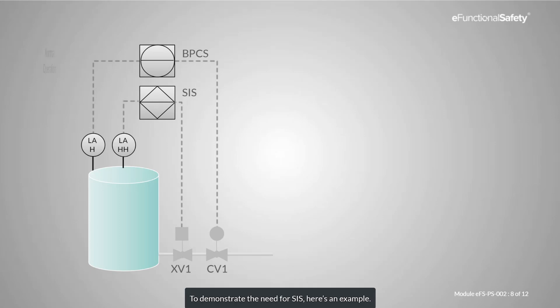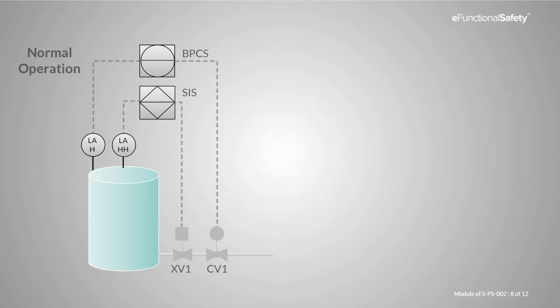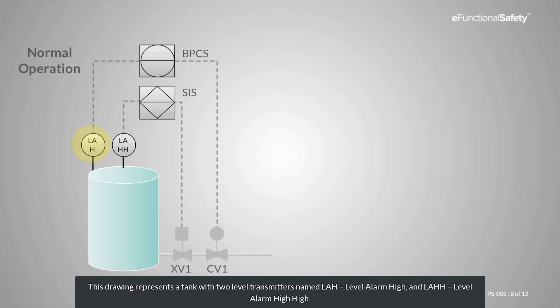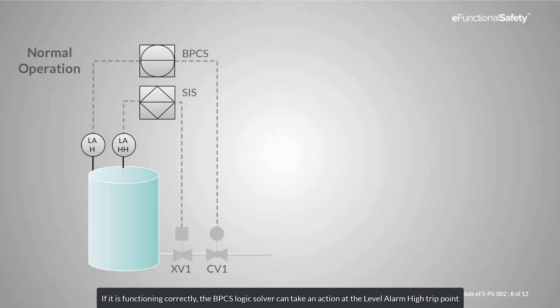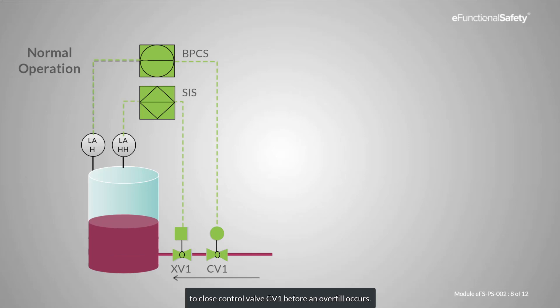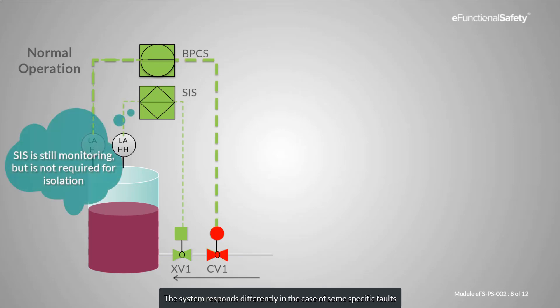To demonstrate the need for SIS, here's an example. This drawing represents a tank with two level transmitters named LAH and LAHH. Each transmitter is connected to separate logic solvers — one for basic process control, the other for safety. If it's functioning correctly, the BPCS logic solver can take an action at the level alarm high trip point to close valve CV1 before an overfill occurs. The system responds differently in the case of some specific faults that the functional safety standards call dangerous failures.